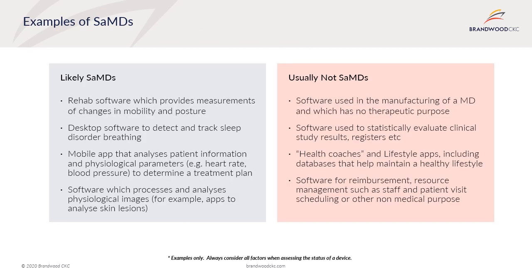Likely software as a medical device examples include rehab software which provides measurements of changes in mobility and posture, desktop software to detect and track sleep disorder breathing, a mobile app that analyzes patient information and physiological parameters such as heart rate and blood pressure to determine a treatment plan, and software which processes and analyzes physiological images, for example apps to analyze skin lesions. Unlikely examples include software used in the manufacture of medical devices with no therapeutic purpose, software used to statistically evaluate clinical study results, health coaches and lifestyle apps, and software for reimbursement or resource management such as staff and patient visit scheduling.